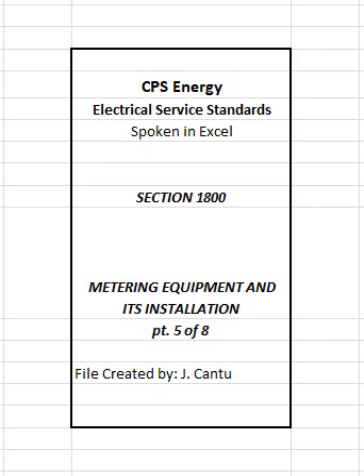1807.4 Width of working space. The width of the working space in front of the electrical equipment shall be the width of the equipment or 30 inches, whichever is greater. In all cases, the workspace shall permit at least a 90-degree opening of equipment doors or hinged panels.